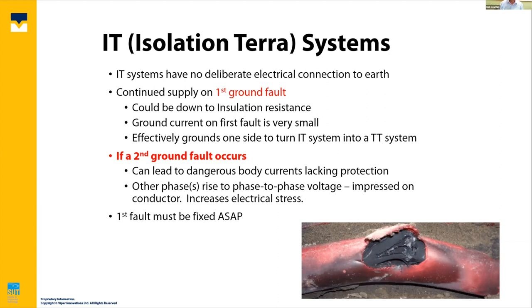The ground current should be very small. I say that with a caveat, and I do have a second presentation on this, but once you get to long umbilicals with a high capacitance, you can and do end up with very high ground currents on a first fault. Theoretically, if you just look at the schematic, you don't see why, but if you start building up the cable or the umbilical with a lumped model showing the inductance and the capacitance, you can quite easily prove that you can get a very high fault current on a first ground fault. If a second ground fault occurs, so this is a key thing now with industrial applications, it can lead to potentially dangerous body currents.